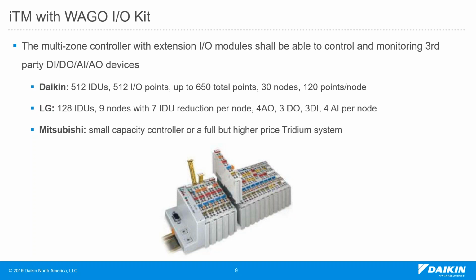If you think about scalability and how you can put that in a different job site or in different location in different nodes and add all of this data to the ITM, that's giving the ITM itself higher advantage versus competitors. So in LG, they can add 128 indoor units. They can use their extended IO module. They can add up to 9 nodes, 7 indoor units per node, and that will give them some limitation in that node. So each node has 4 analog output, 3 digital output, 3 digital inputs, and 4 analog input. It's not scalable like our node.